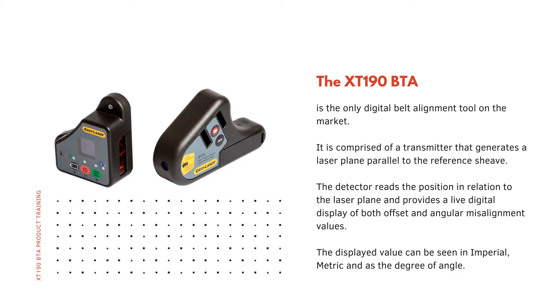The XT190 is the only digital belt alignment tool on the market. It is comprised of a transmitter that generates a laser plane parallel to the reference sheave. The detector reads the position in relation to the laser plane and provides a live digital display of both offset and angular misalignment values. The displayed value can be seen in imperial, metric, and as the degree of angle.